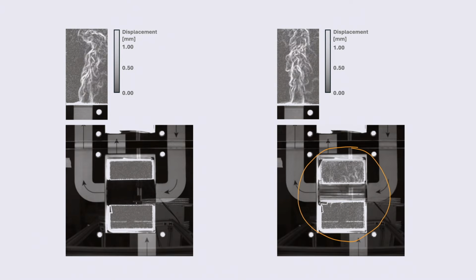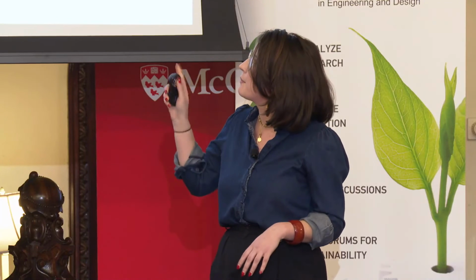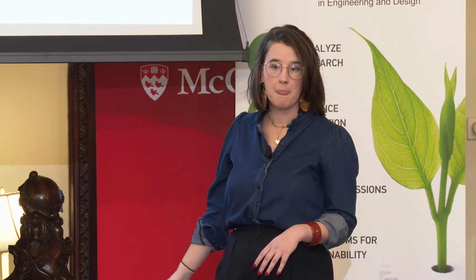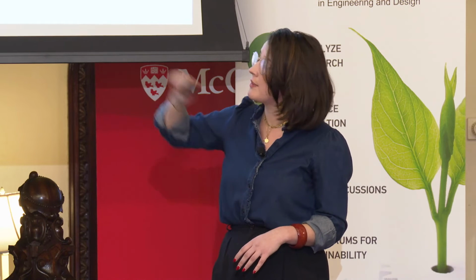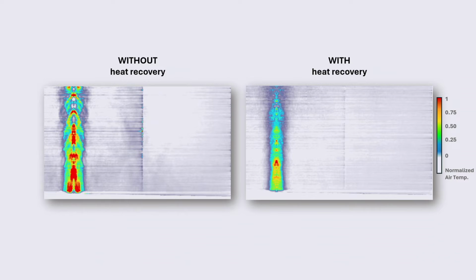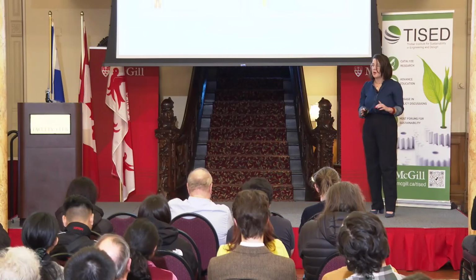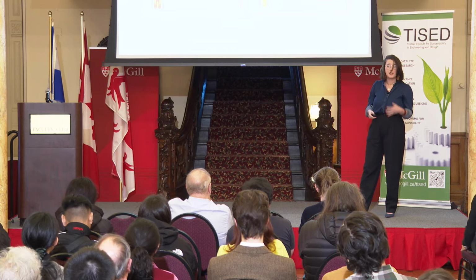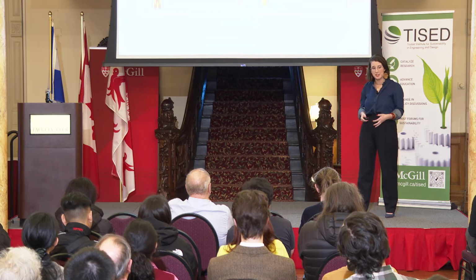Really, the smoking gun for heat recovery is the temperature of those exhaust plumes. In the control, the exhaust temperature is comparable to the warmest point in the system—all that energy is just vented into the atmosphere. But in the experiment, the exhaust temperature is significantly reduced because that energy is being recovered back into the system. We measured a heat recovery efficiency of about 38% for the small-scale model, but other and full-scale configurations could reach up to 50% efficiency, just with a careful spatial arrangement.